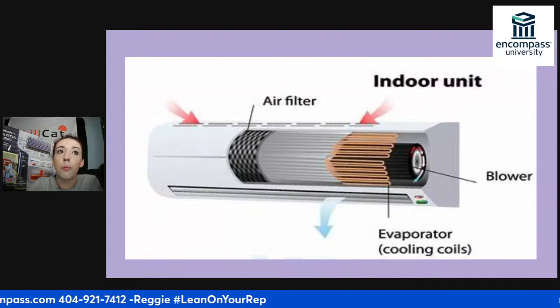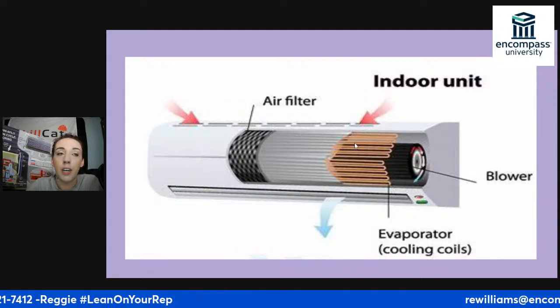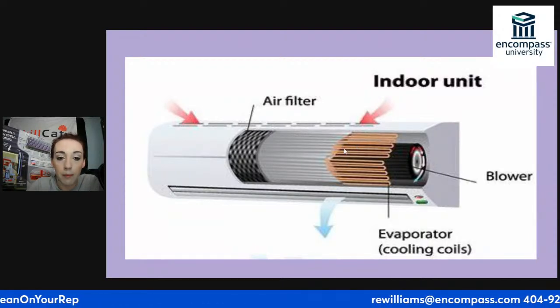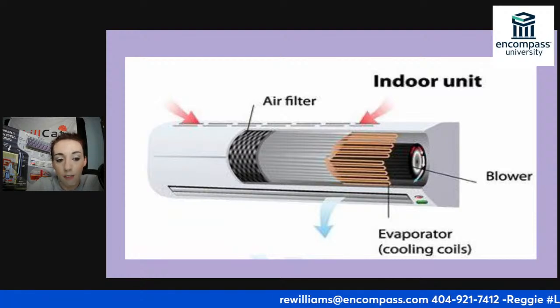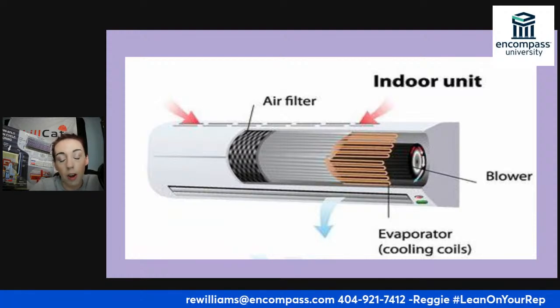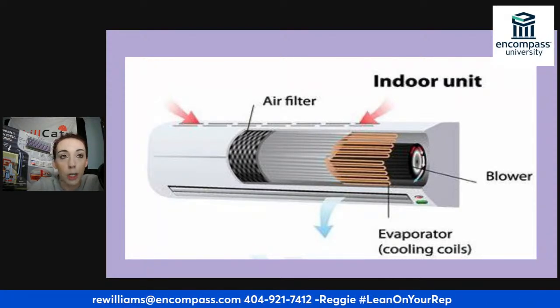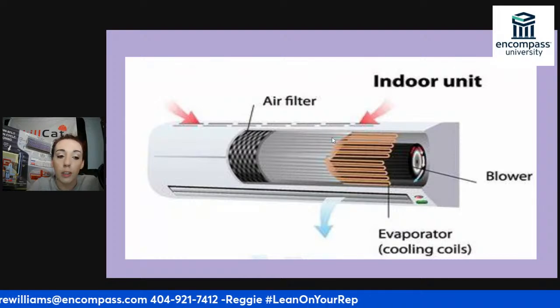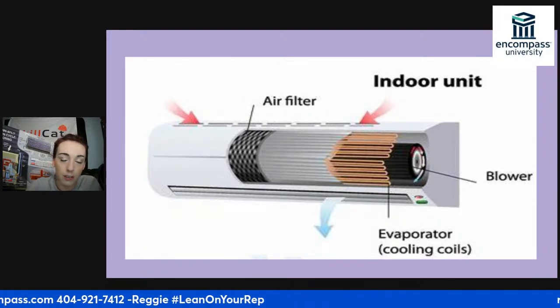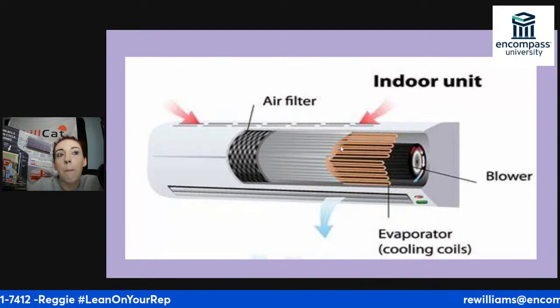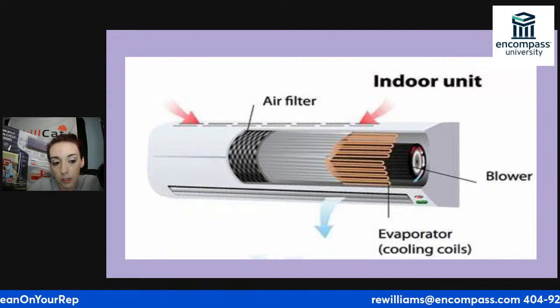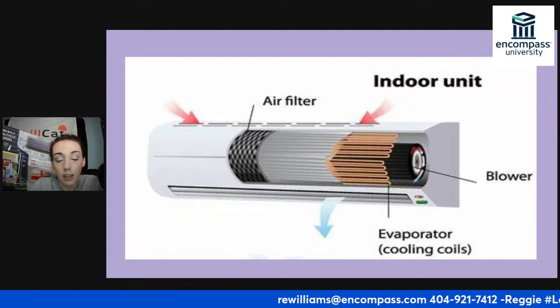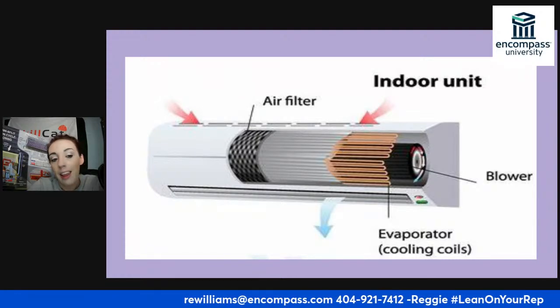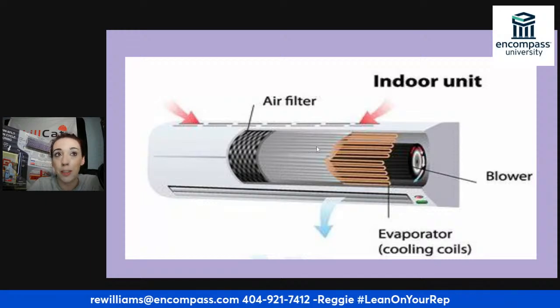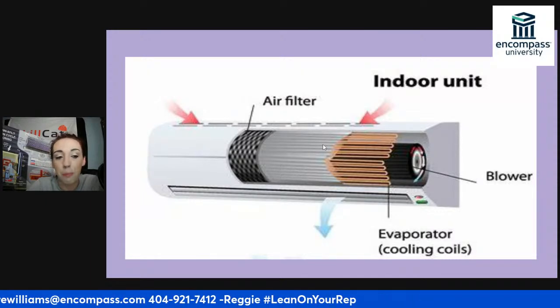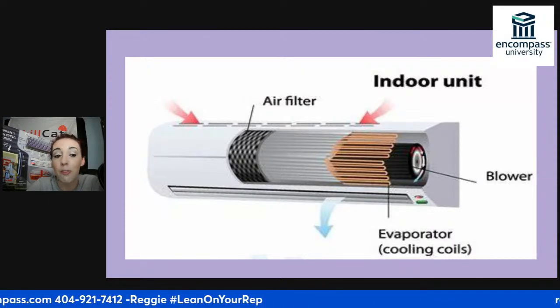Because we need so much more surface area than what we're given in a mini split, cleaning becomes more important. We typically tell customers, whether residential or commercial, to do a quarterly cleaning on their AC units. With mini splits, we need to bump that up a little bit if it's one of those situations where we know the coil gets dirty faster, because every time we have a dirty mini split indoor coil, we will have a breakdown. It's not a matter of if, it's a matter of when.